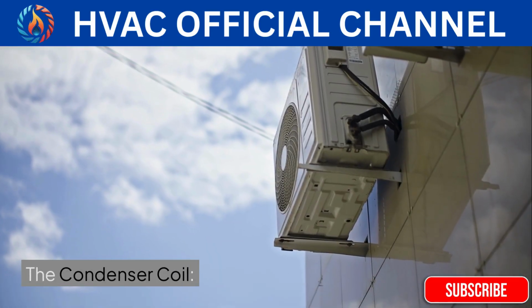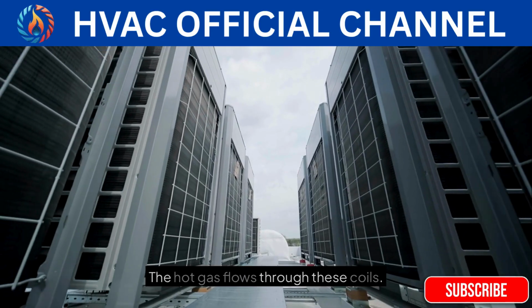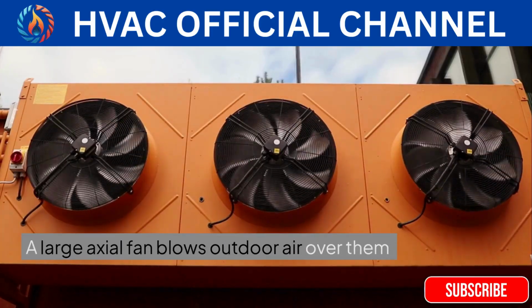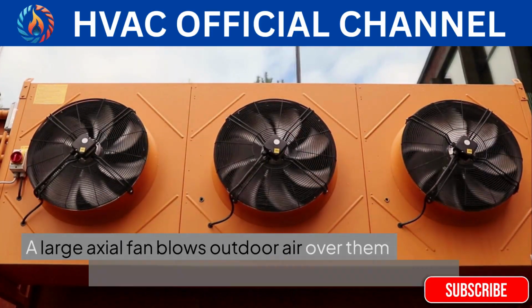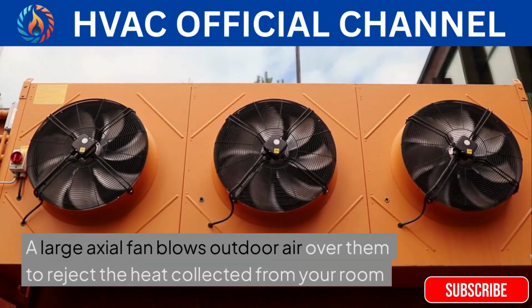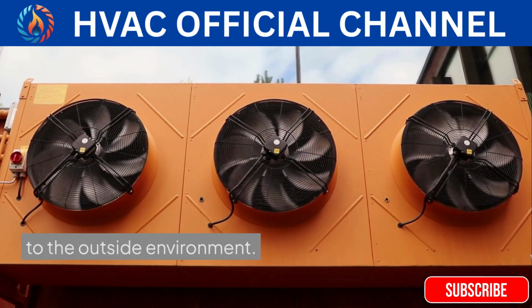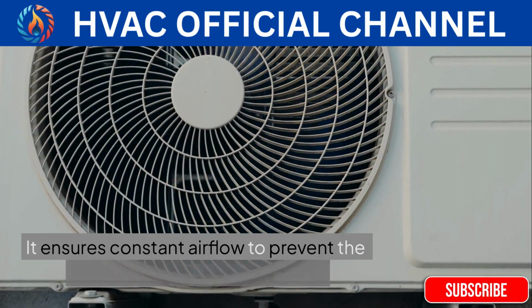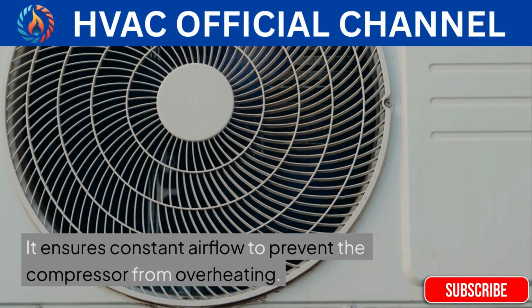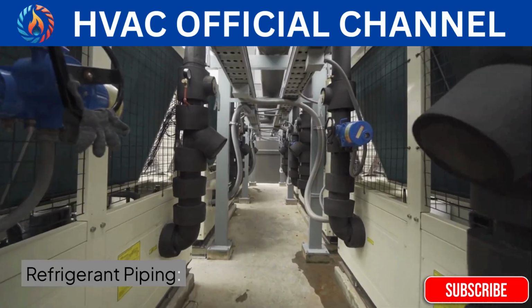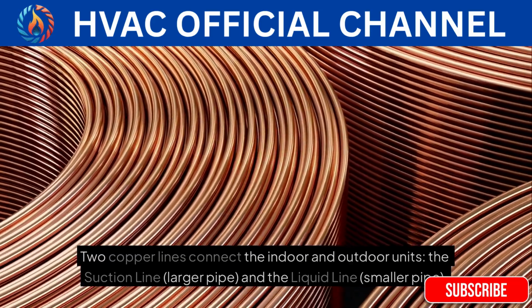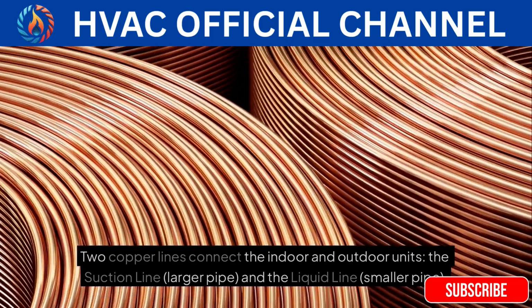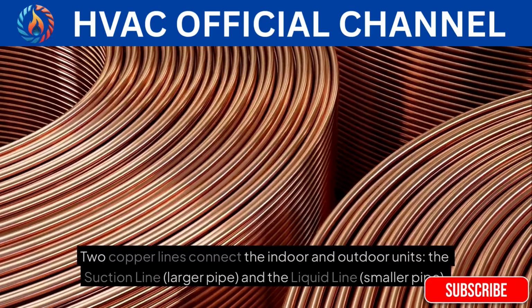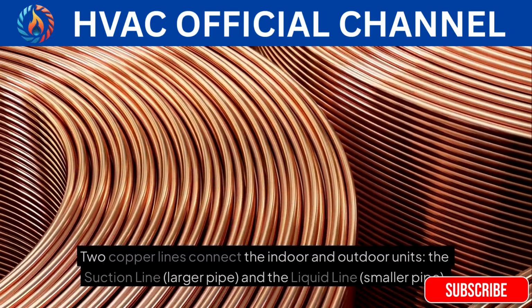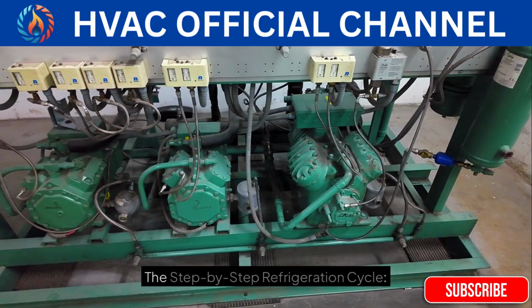The condenser coil. The hot gas flows through these coils. A large axial fan blows outdoor air over them to reject the heat collected from your room to the outside environment. The fan motor. It ensures constant airflow to prevent the compressor from overheating. Refrigerant piping. Two copper lines connect the indoor and outdoor units, the suction line, the larger pipe, and the liquid line, the smaller pipe.